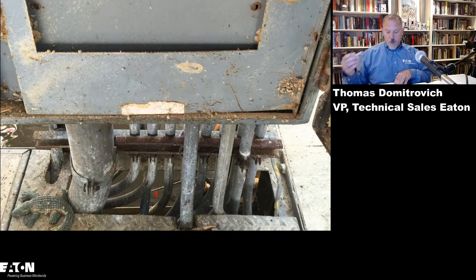Common supply equipment: where feeder conductors originate in the same panel board, switchboard, or other distribution equipment, and each feeder terminates in a single disconnecting means, not more than 6 feeders shall be permitted. So I can now bring multiple feeders out to that pier.